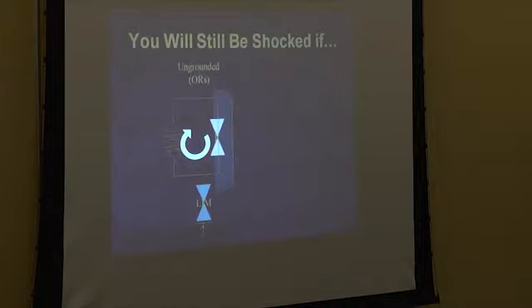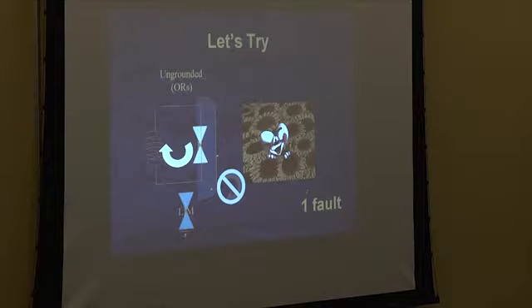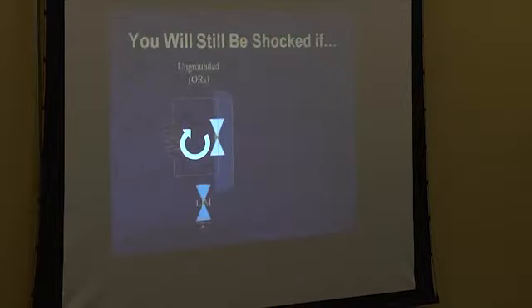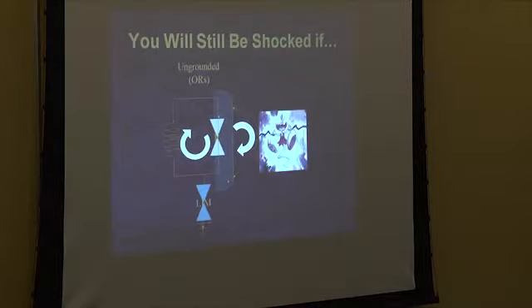So no shock — but that's no shock with one fault. The reason you have to be careful is if there are two faults. So let's create two faults: here's one fault here, and another fault in the casing over here. Now the circuit is completed, and you can get shocked. So if there are two faults, the line isolation monitor won't protect you — there is no foolproof system.